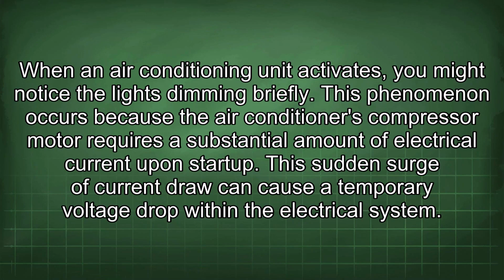When an air conditioning unit activates, you might notice the lights dimming briefly. This phenomenon occurs because the air conditioner's compressor motor requires a substantial amount of electrical current upon startup. This sudden surge of current draw can cause a temporary voltage drop within the electrical system.